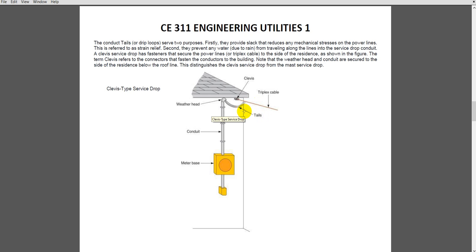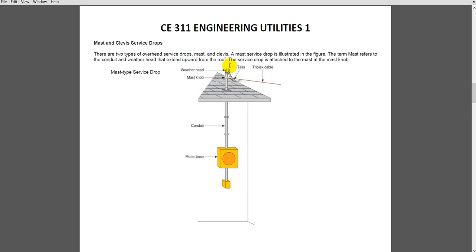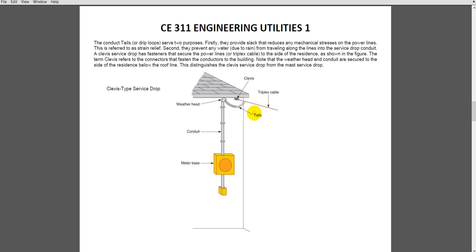So, our triplex cable comes here, and the tap for the source goes to the weatherhead from this clevis. They provide slack that reduces mechanical stress and they prevent any water from traveling along the lines. The water drips here instead, and it is safe here under the roofing of the house. So when the rain drips, it drops here, instead of rising up to the service at the weatherhead. Compared to this one, where rain can hit our weatherhead. It has no roofing, so this one is preferred.